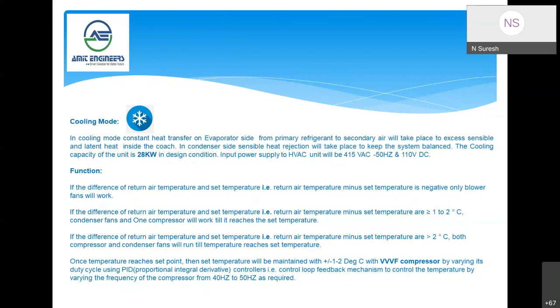As told, this unit is around 28 kilowatt design condition, and the unit will function on 415 volt, 50 hertz and 110 volt DC, whereas we have an inbuilt converter to give a 24 volt DC output to function the switch gears and all.